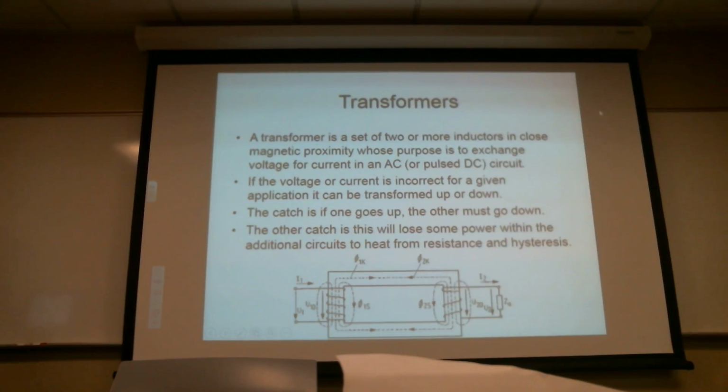No moving parts. About the only thing that damages these things is too much current. I think the other thing that probably can occur, copper in and of itself, if it's well protected from oxygen, doesn't change too much over time, over many, many years. The insulation, on the other hand, could break down because that's usually made out of some organic compound that, over months isn't a problem, over a few years isn't a problem, but over 150 years, for some really long period of time, the insulation does eventually start to break down.